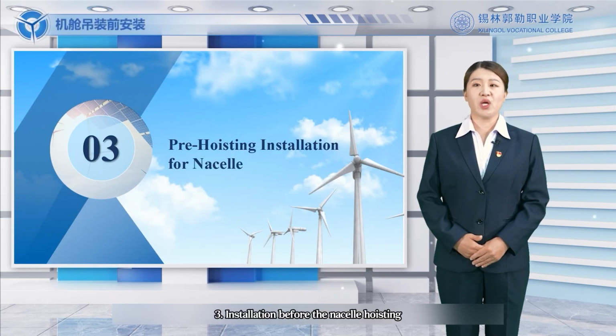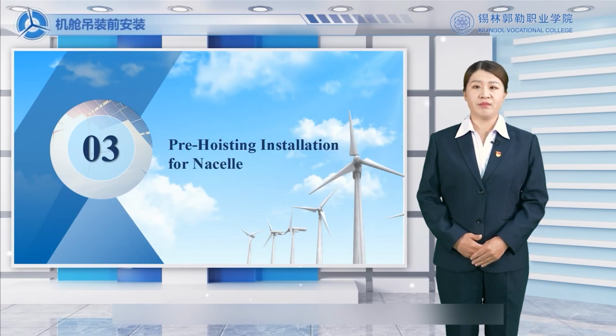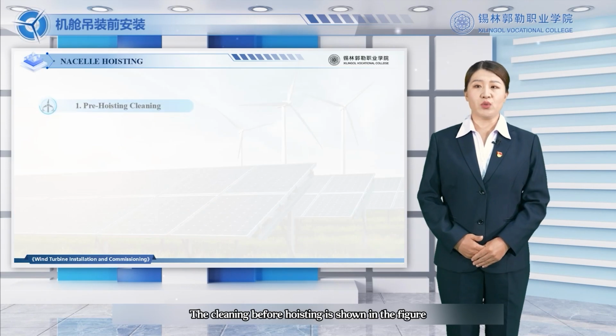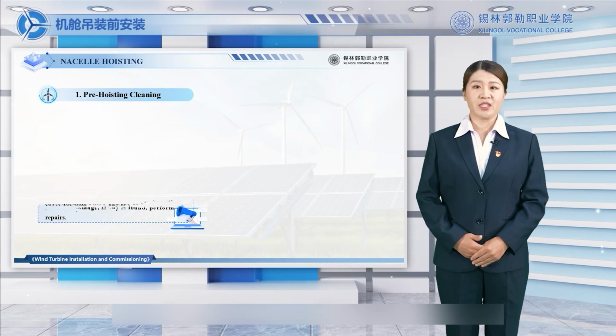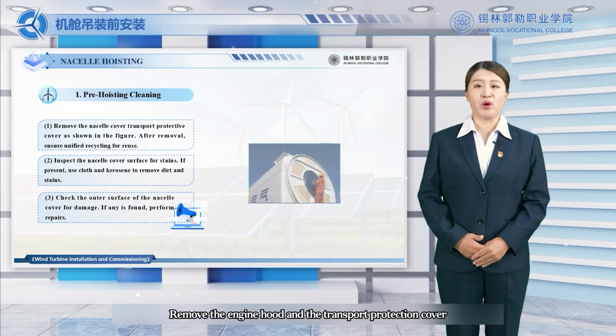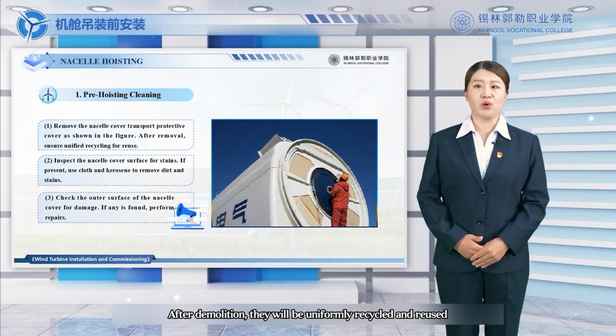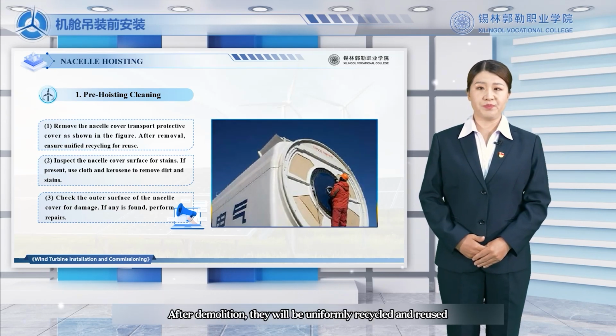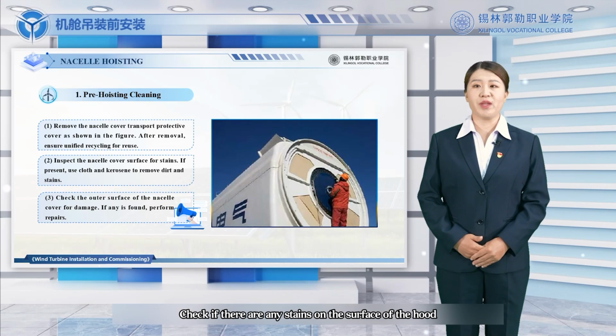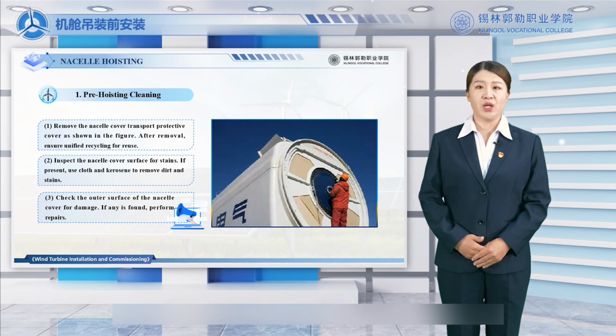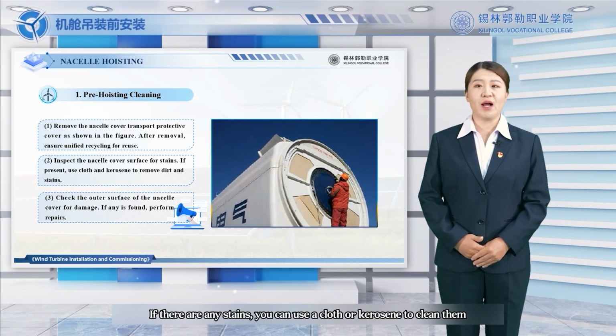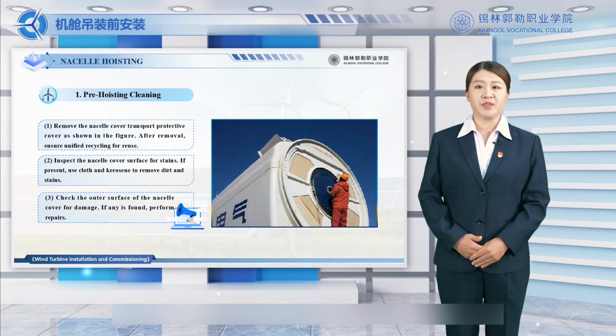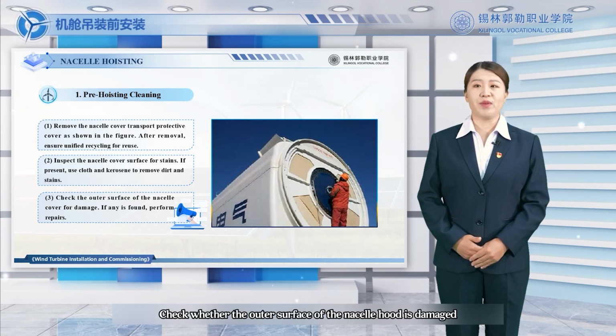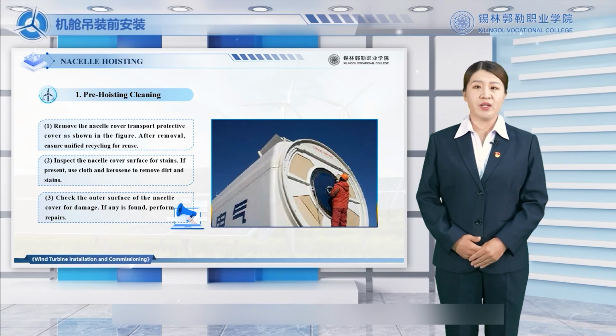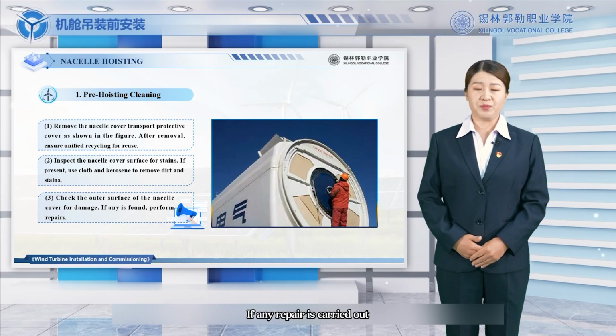3. Installation before the nacelle hoisting. The cleaning before hoisting is shown in the figure. Remove the engine hood and the transport protection cover. After removal, they will be uniformly recycled and reused. Check if there are any stains on the surface of the hood. If there are any stains, you can use a cloth or kerosene to clean them. Check whether the outer surface of the nacelle hood is damaged. If so, carry out repairs.